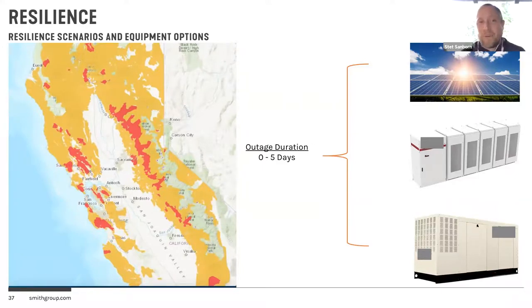And wildfires are not going away in California. They're only getting worse, and we could go into a whole thing of why that is. But the main thing is most clients now are jumping onto the generator bandwagon. That's producing a ton of cost, and it's also defeating the emissions-free goal of electrification. If you have all these distributed generators with marginal emissions, that's way dirtier than actual grid power and definitely dirtier than what we could generate on site. But you have to come to the table with a full financial analysis to say, can I provide you a better solution?